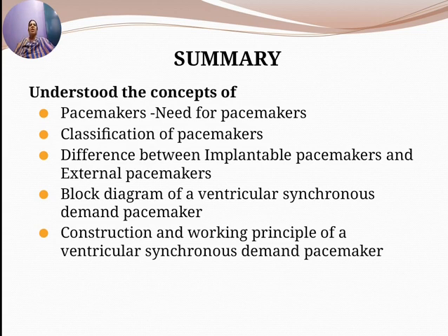So, the R wave inhibited pacemaker allows the heart to pace at its normal rhythm. If the R wave is missing for a preset period of time, the pacer will supply the stimulus. Therefore, if the heart rate falls below the predetermined minimum, the pacemaker will turn on and provide the heart a stimulus. For this reason, it is called demand pacemaker.